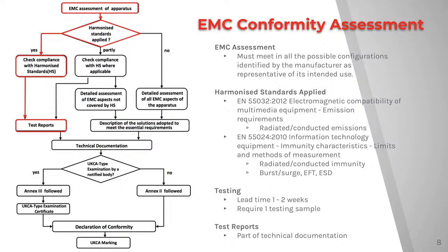So moving on with the EMC conformity assessment process. For the initial EMC assessment, you must meet the requirements in all of the possible configurations identified by the manufacturer as representative of its intended use. With the harmonized standards that are applied, there are many different harmonized standards, but here are a few examples. We have EN 55032:2012, Electromagnetic Compatibility of Multimedia Equipment Emissions Requirements, and this is for radiated or conducted emissions. And then we also have EN 55024:2010, Information Technology Equipment Immunity Characteristics, Limits and Methods of Measurement, which covers radiated/conducted immunity, and burst/surge, EFT and ESD.